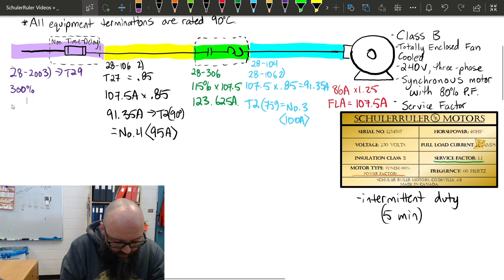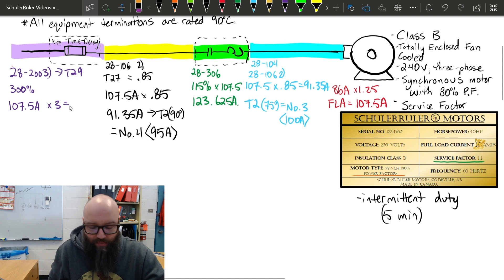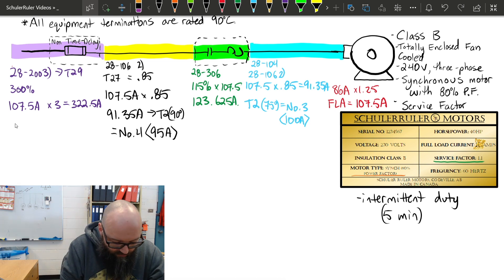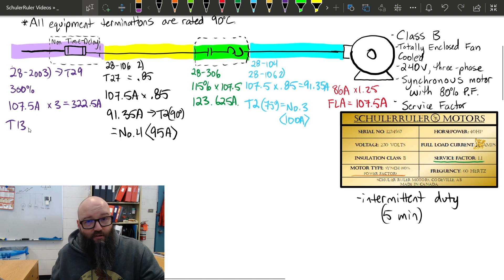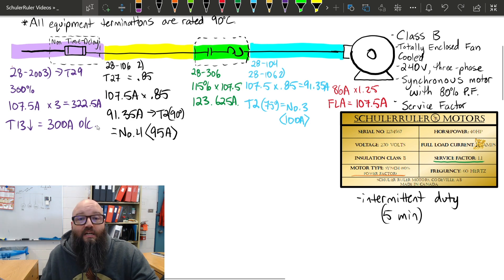In this case, we're just going to run the numbers. We're looking at 107.5 amp FLA times 3 gives me a maximum calculated value or maximum calculated trip setting of 322.5 amps. I cannot exceed this. I have to go to table 13 if I'm selecting an overcurrent device. Because I cannot exceed this, there is no 322.5 on table 13. I have to go down. I go down at table 13 and I select a 300 amp overcurrent device. That would be the max size device that I can put on that branch circuit to protect that synchronous motor.